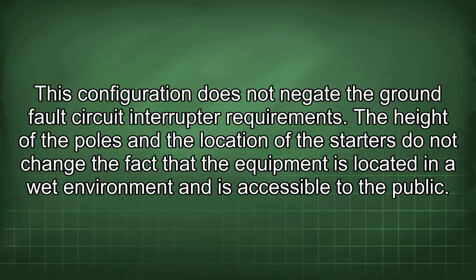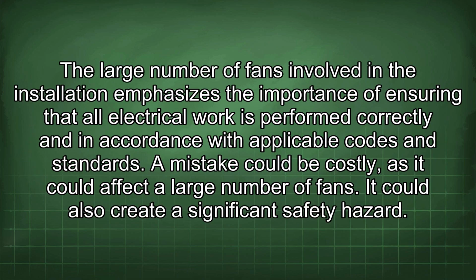The height of the poles and the location of the starters do not change the fact that the equipment is located in a wet environment and is accessible to the public. The large number of fans involved in the installation emphasizes the importance of ensuring that all electrical work is performed correctly and in accordance with applicable codes and standards. A mistake could be costly, as it could affect a large number of fans. It could also create a significant safety hazard.